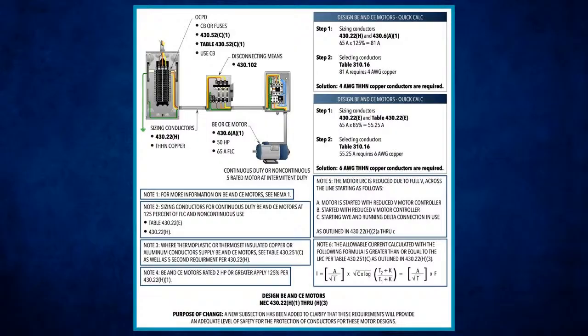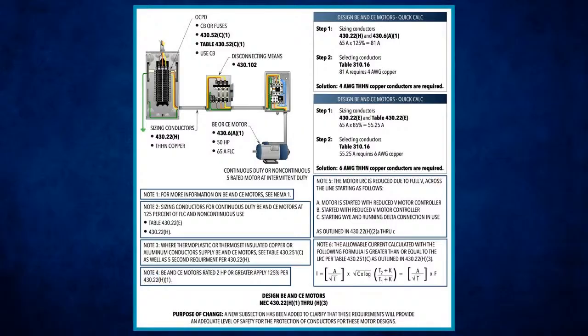Now, without doing anything else, I said you can go up to the next standard size, and you're going to look just right below that at 430.52(C)(1) Exception 1. If it won't allow the motor to start due to inrush current, for instance, then you can go up to the next standard size. The next standard size in Table 240.6(A) is going to be 175 amp. So we've established 150 and 175 amp at this point.